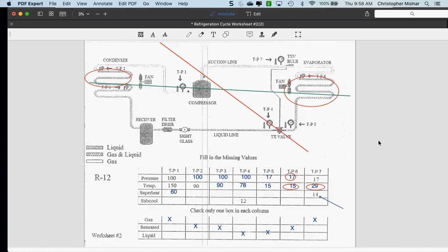If my statement that I just made is true, the more refrigerant in the evaporator, the more heat I can absorb. Why don't I want a superheat of 0? The evaporator will freeze up, right? Think about the level of liquid. Let's not think about freezing. A superheat of 0 just tells me I don't have any sensible heat gain, which would tell me my evaporator is completely full of liquid refrigerant. Why don't I want a superheat of 0?